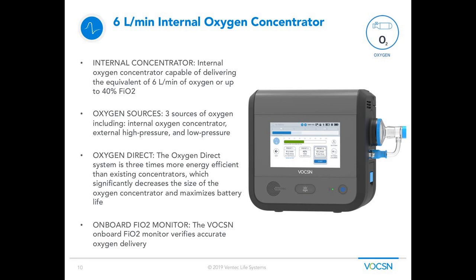This is the first and only system in the world to combine ventilation and oxygen together into one comfortable breath for the patient. Traditionally, you'd have two separate devices, trying to sync those two devices together to deliver that oxygen. You'd be losing a lot of the oxygen out the leak or the exhalation valve of the circuit. You're not actually certain how much oxygen is getting to the patient. With VOCSN, we're making the oxygen and delivering it directly to the patient. We know exactly how much we're making, exactly how much we're delivering - much more efficient and effective use and delivery of the oxygen with VOCSN. So that's one of the benefits when we talk about integrated respiratory care - the integration of ventilation and oxygen.